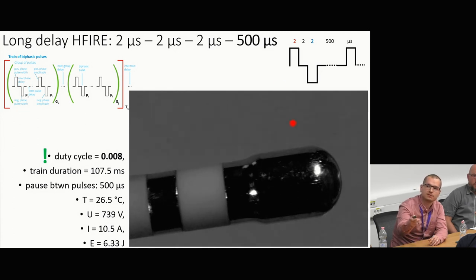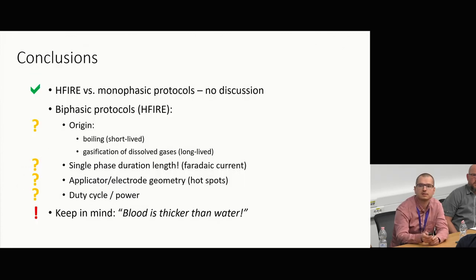Now, how to mitigate this? Well, we can take a longer pause between two consecutive pulses. We get a much lower duty cycle, in this case with much lower power, so the same energy is delivered over a longer period of time. There's practically no bubble formation, and definitely no boiling. So it's all down to the protocol in this case.